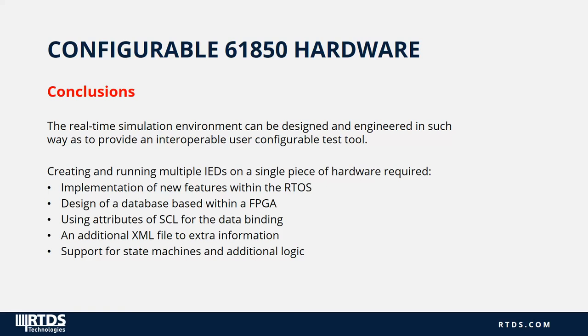Conclusions. The real-time simulation environment can be designed and engineered in such a way as to provide an interoperable user-configurable test tool. Creating and running multiple IEDs on a single piece of hardware required some implementation of new features within the real-time OS, including the design of a database based within an FPGA. We also required using the attributes of SCL for the data binding, an additional XML file to store information not part of SCL, and support was added for state machines and additional logic.